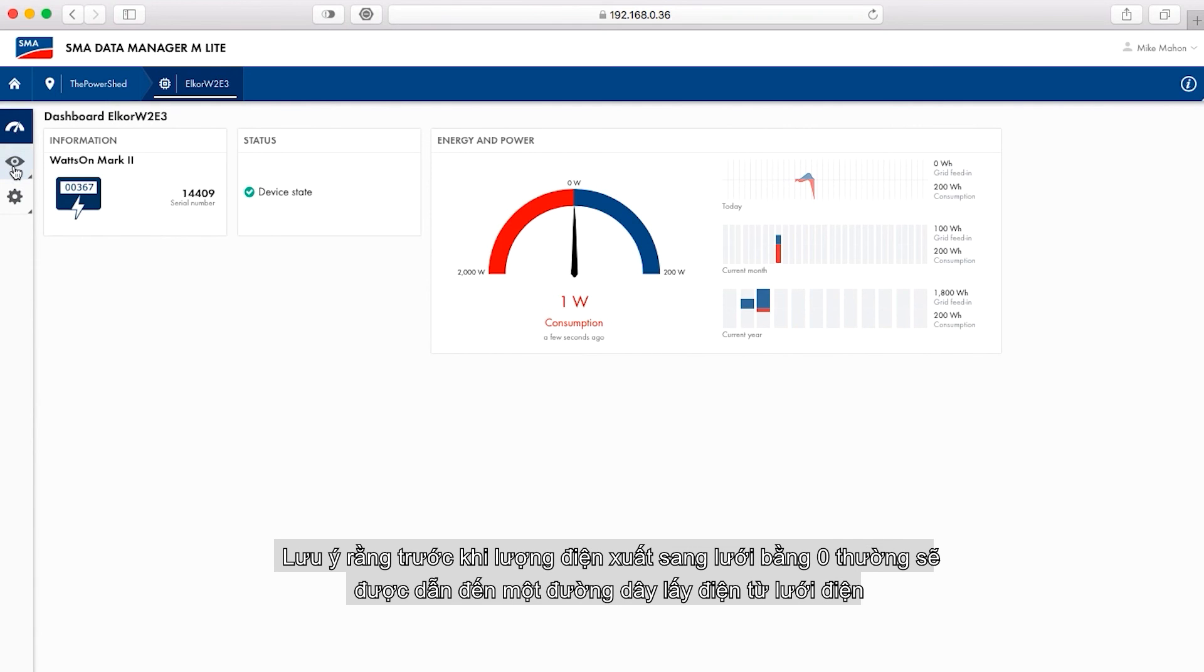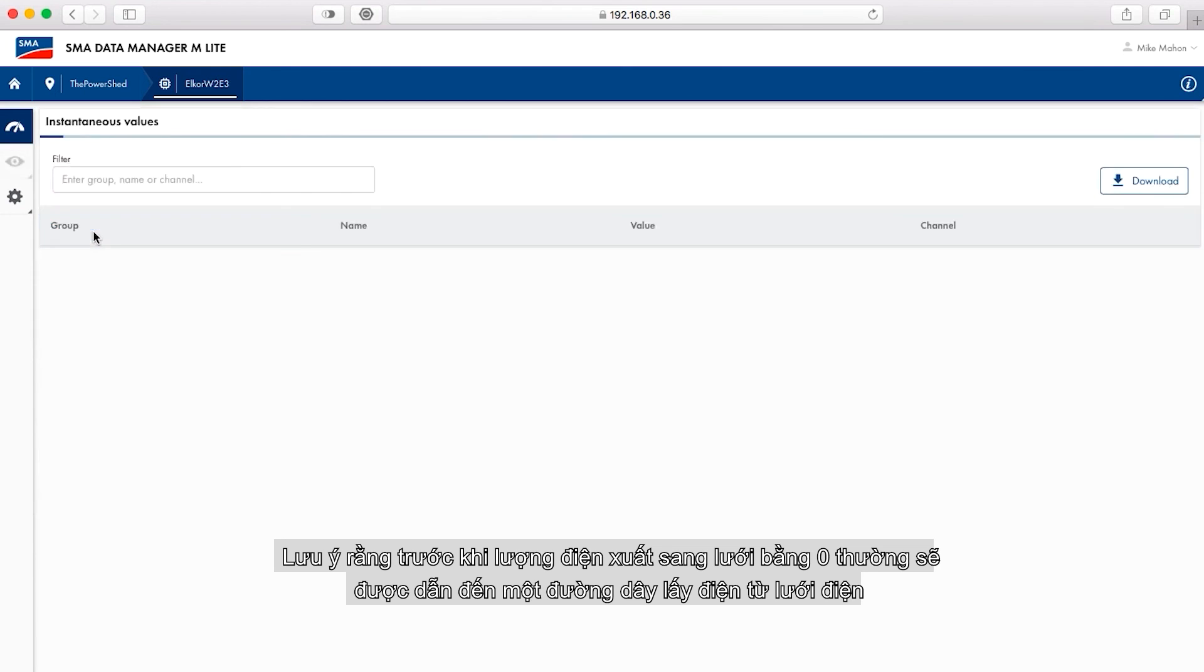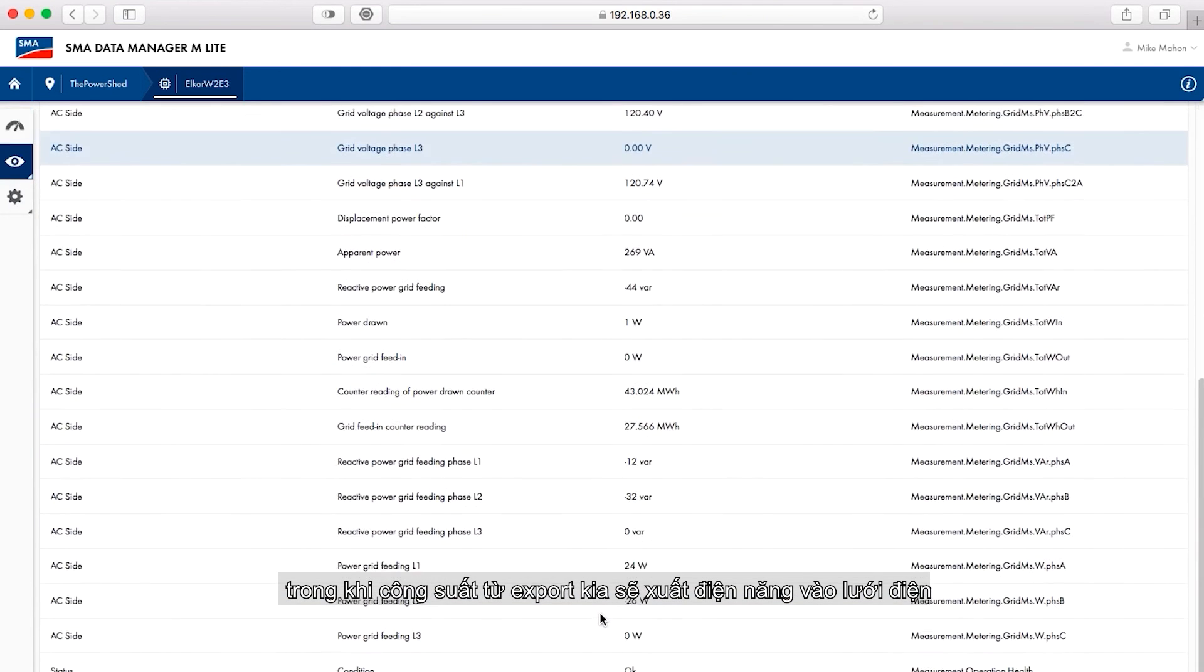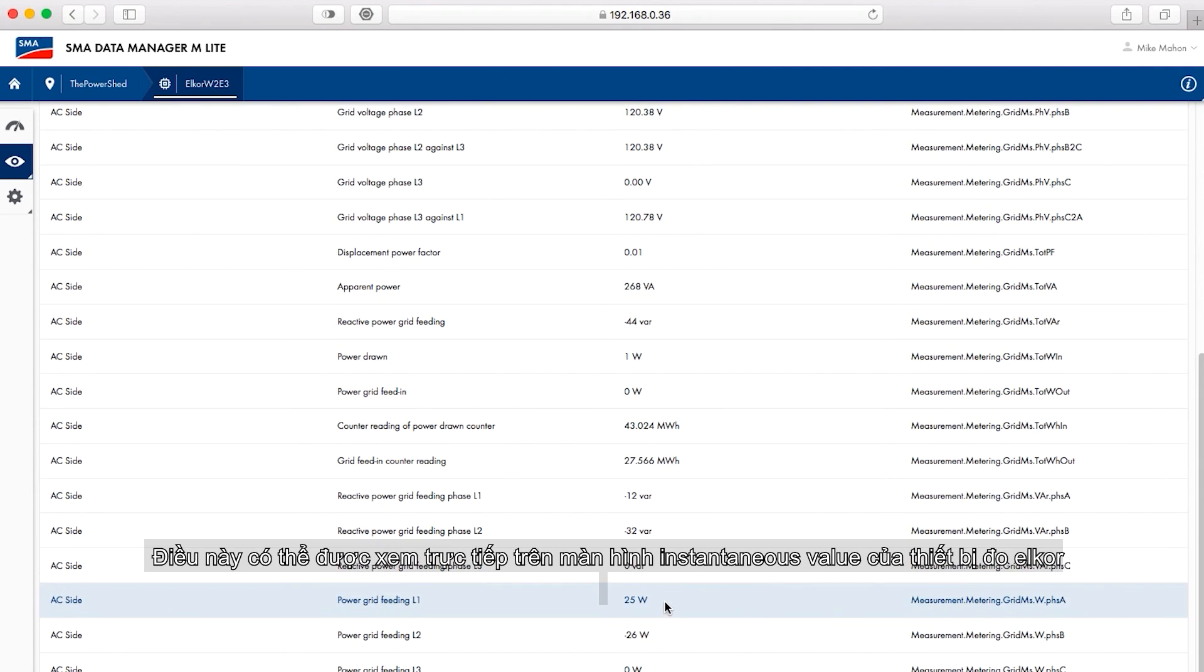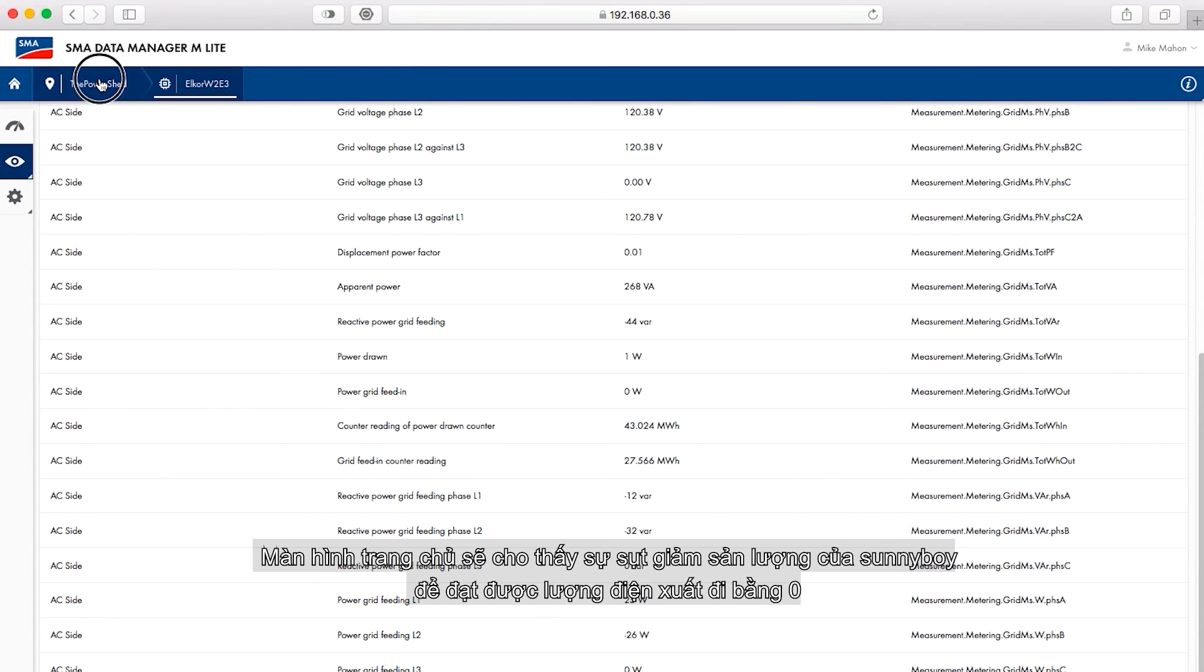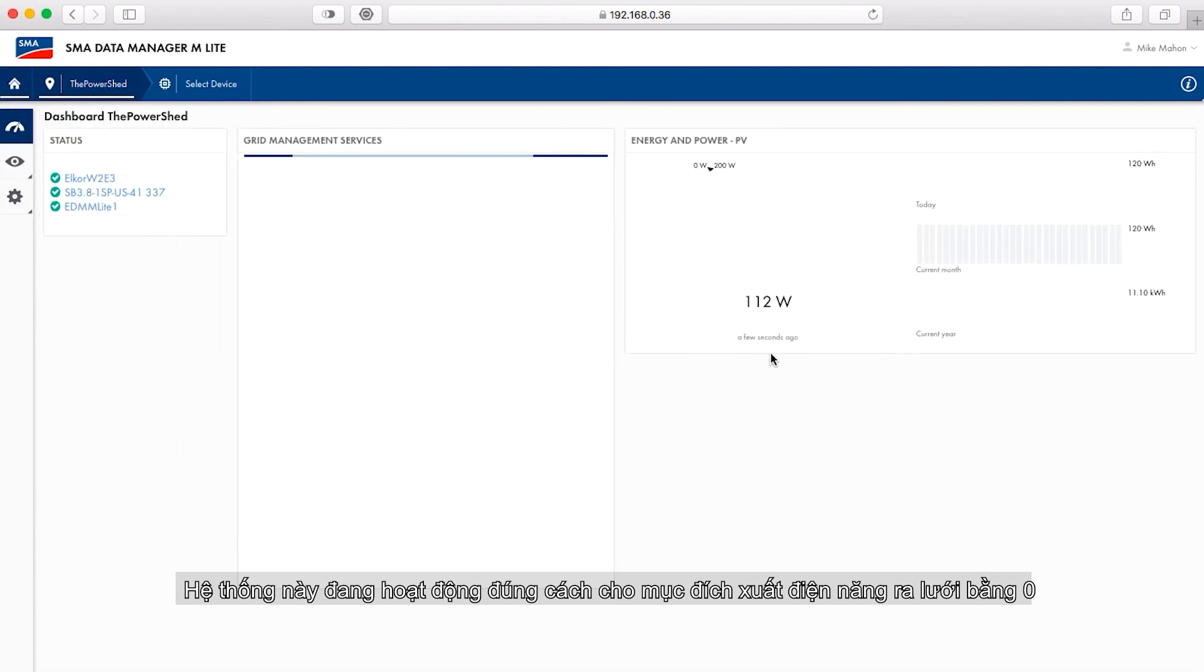Please note that as explained before, the net zero export will usually result in one line drawing power from the grid while the other exports power to the grid. This can be seen directly on the instantaneous value screen of the Elkor meter. The home screen shows the drop in sunny boy production required to achieve net zero export. This system is operating properly for the goal of net zero export.